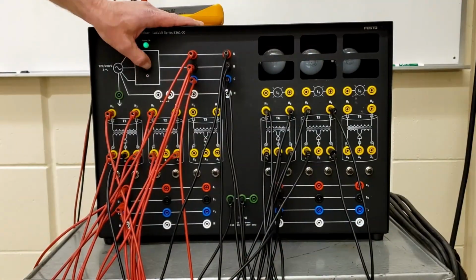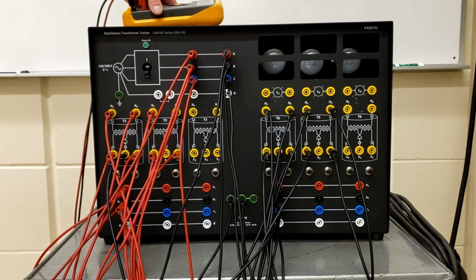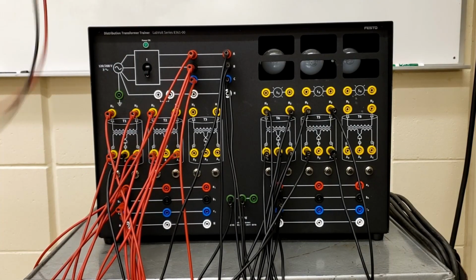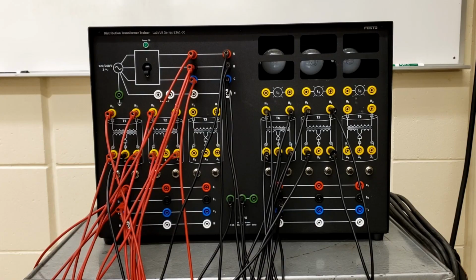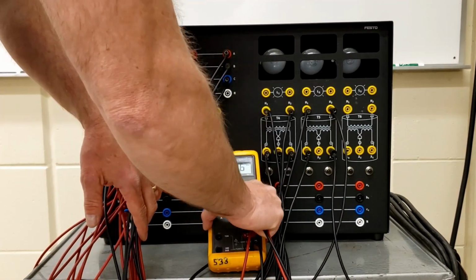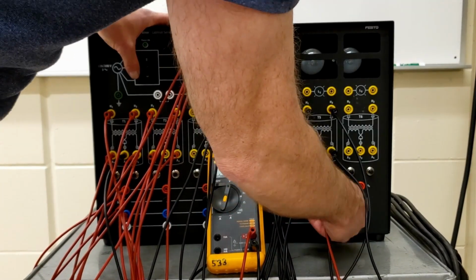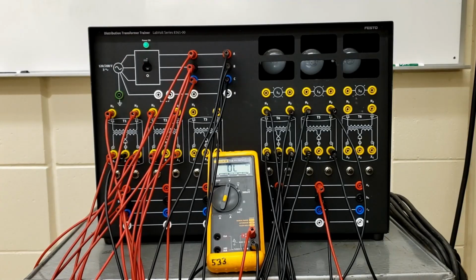Okay, let's turn this on and make sure that we haven't messed anything up. Looks good. And what are we taking? We're looking at A2 and B2. We're looking at our secondary voltages between A2, B2, B2, C2, and C2 and A2. Okay, so on the secondary side, between the phases, so between A and B, we should have 240. Okay, looks good. We got 240 volts there.